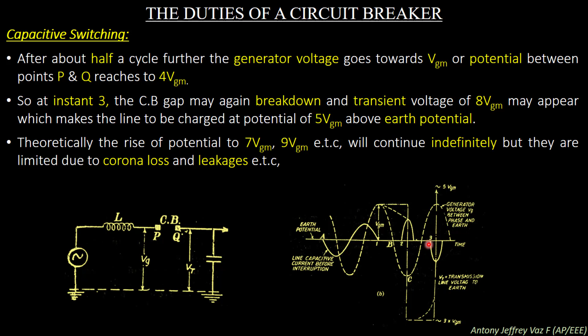Although these extreme conditions caused by capacitive current breaking are improbable and rare, they do sometimes occur, causing serious damage. So this type of multiplying factor in capacitive current breaking is a very extreme condition, and it will cause serious damage in the circuit breaker while interrupting a capacitive switching current. The cause of this type of voltage transient is the inability of the circuit breaker to provide adequate dielectric strength in the gap after current interruption. So you can see the multiplying process of current.